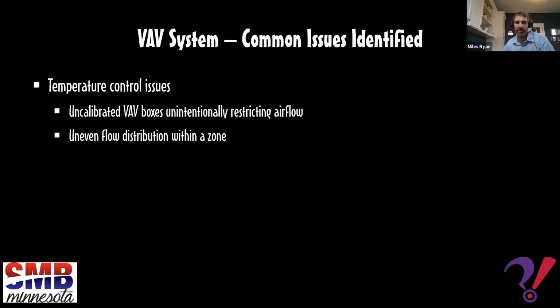As it turned out, they hadn't actually finished the TAB work prior to us coming in and functionally testing, but we had a unique timeline that we had to meet there. We don't like to do functional performance testing prior to TAB, but sometimes it happens. Ultimately, once the TAB contractor came in, they were able to make some adjustments to the diffusers and more evenly distribute the cool air coming out of the diffusers within the space. But up until that point, the person sitting at that workstation was quite uncomfortable.